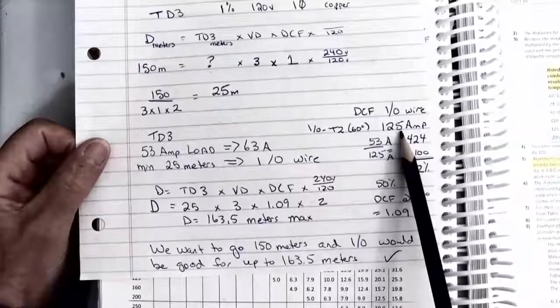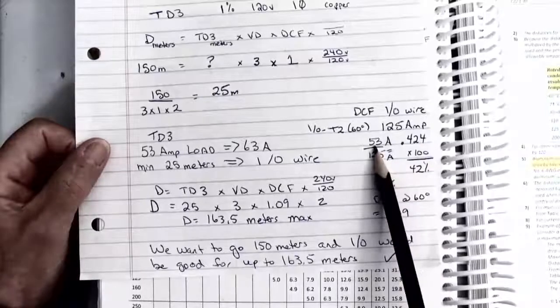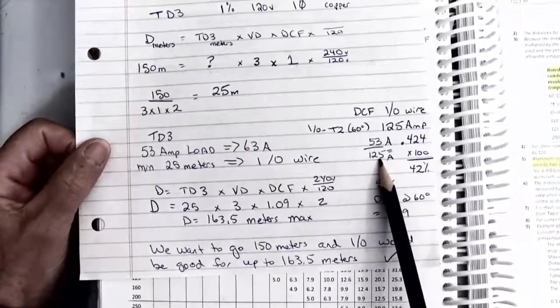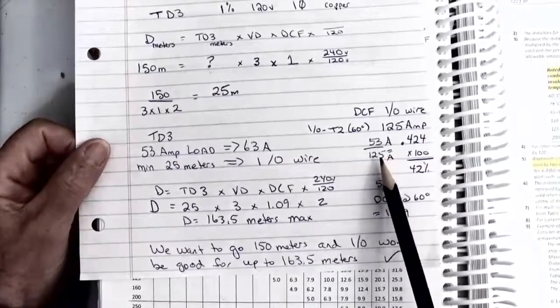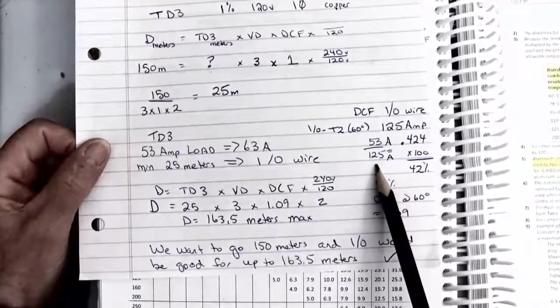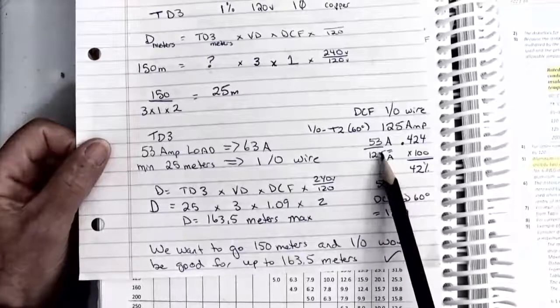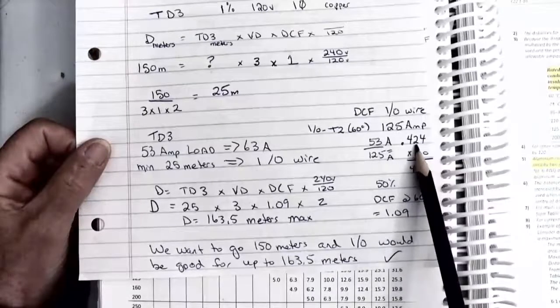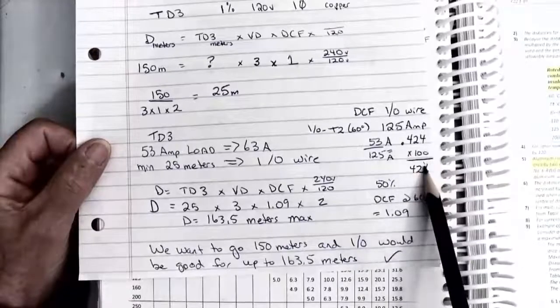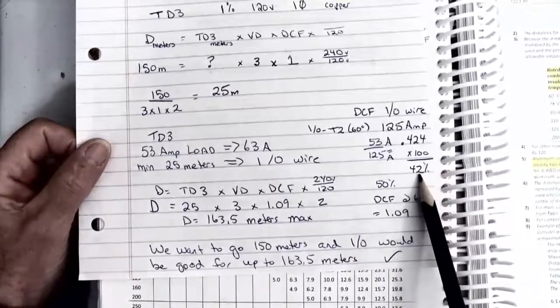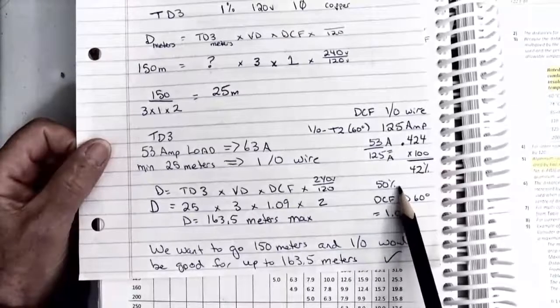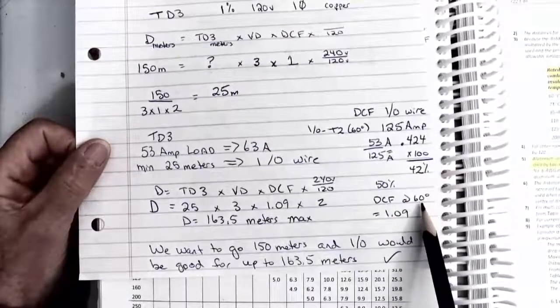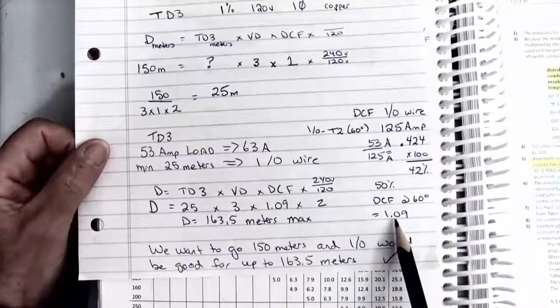In Table 2 I find that a 1/0 wire at 60 degrees is good for 125 amps. My load was 53 amps and the wire is rated for 125 amps — a huge difference. We only need 53 amps running to the load, but we're using a larger conductor to reduce voltage drop and lower resistance. The percentage of the wire's capacity actually being used by the load is 42.4%. Since we must round up and cannot round down, I go to the DCF table and look for 50% usage at 60 degrees, and find that my actual DCF is 1.09.